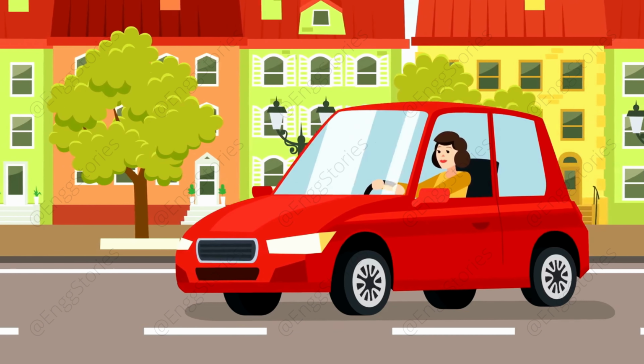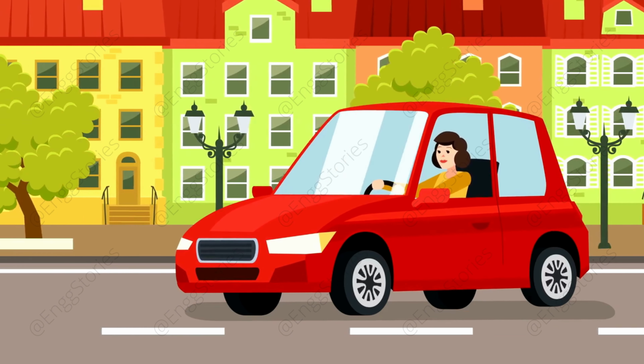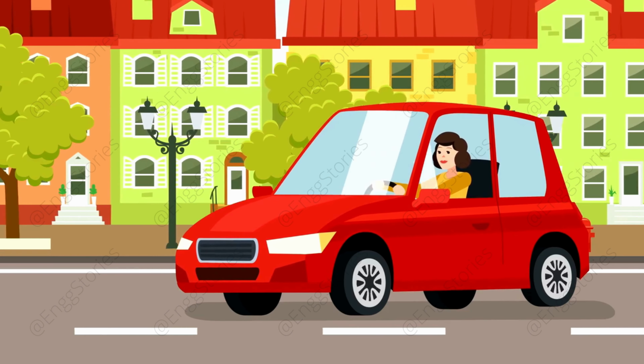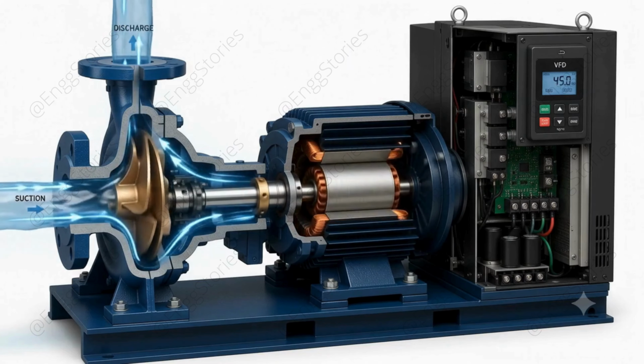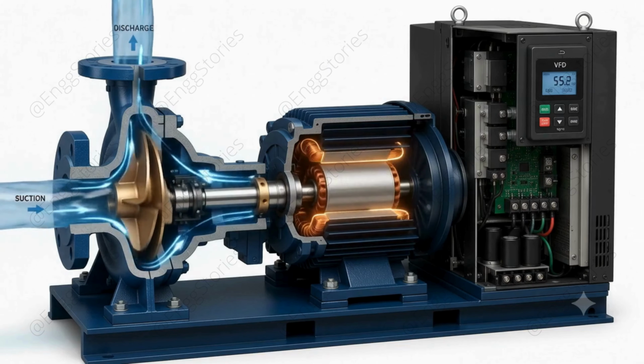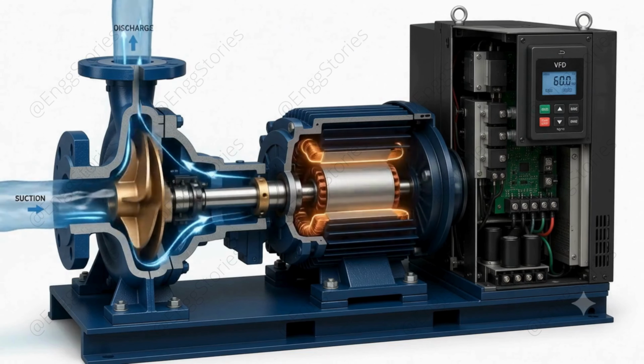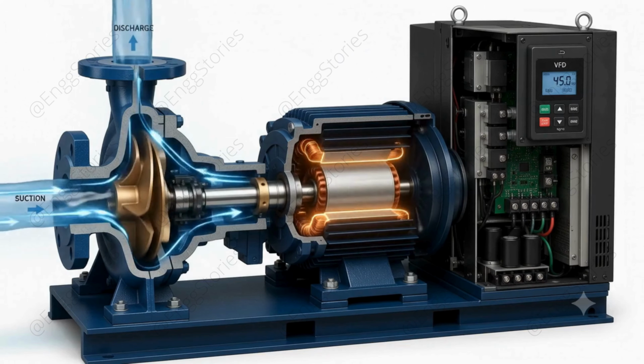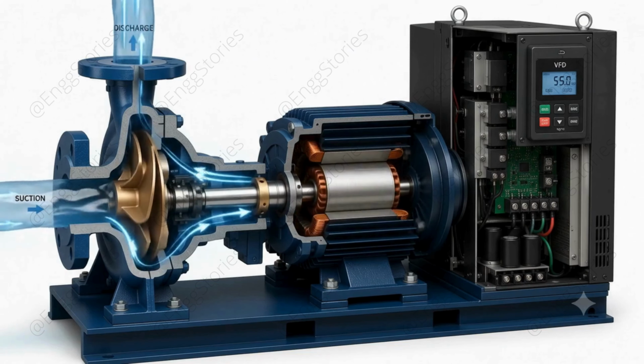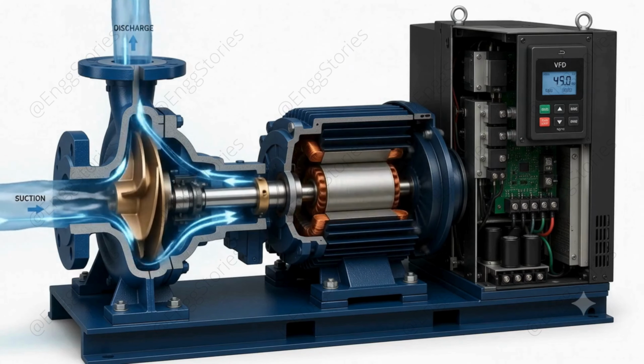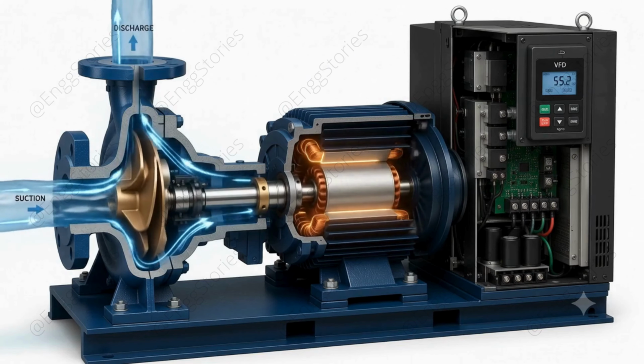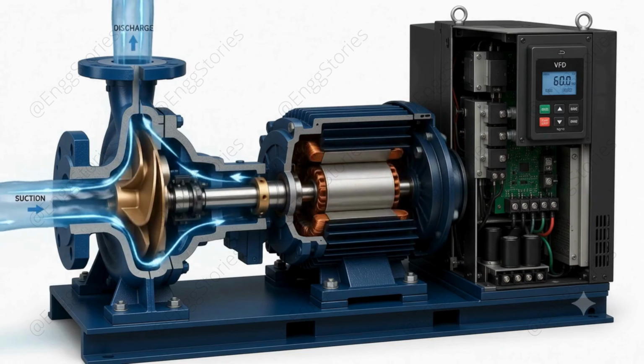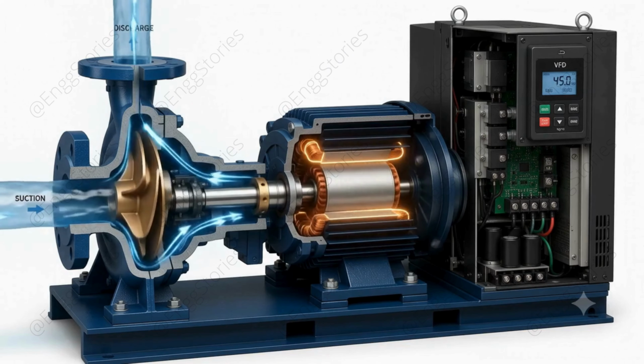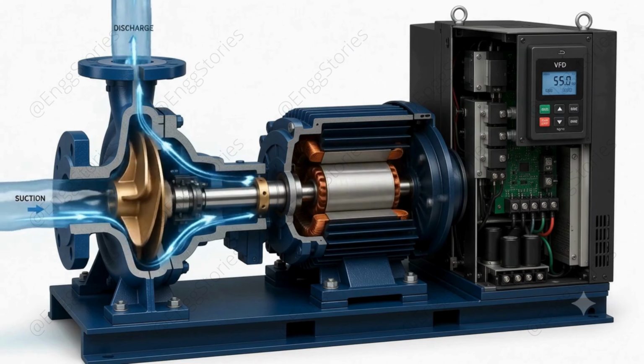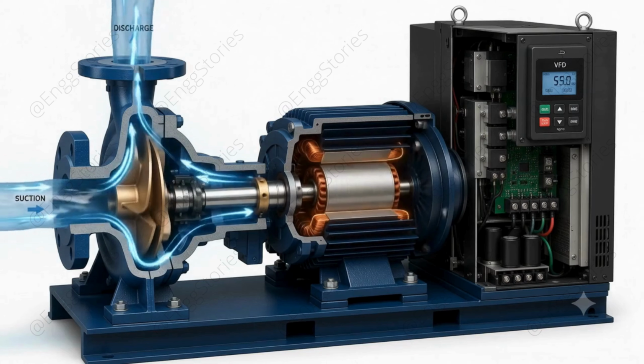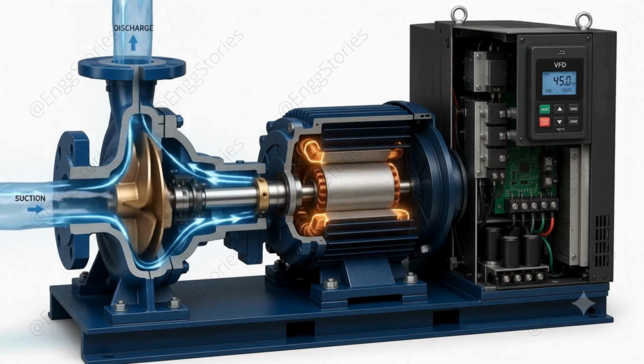When you press the accelerator, the car goes faster. When you ease off, it slows down. A VFD does the same thing for an electric motor. So why do we use a VFD on a pump? A centrifugal pump does not always need to run at full speed. The cooling load in a building keeps changing throughout the day. Sometimes the demand is high, and sometimes it is low. Instead of running the pump at 100% speed all the time, the VFD automatically adjusts the motor speed based on the required water flow.